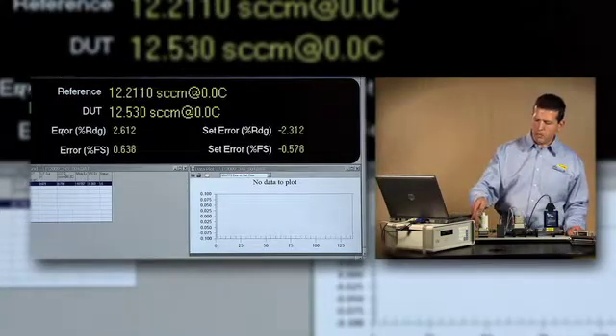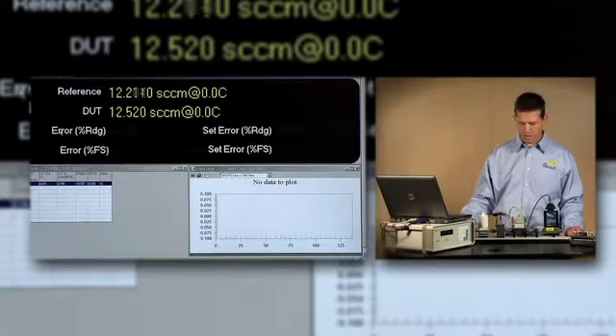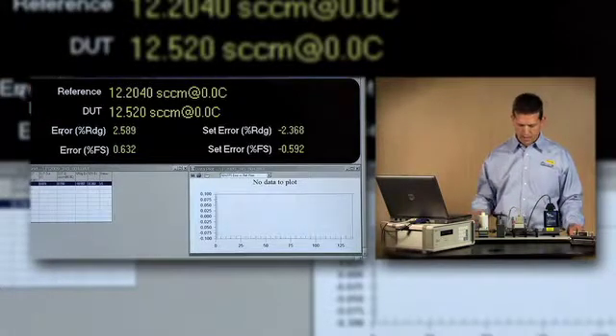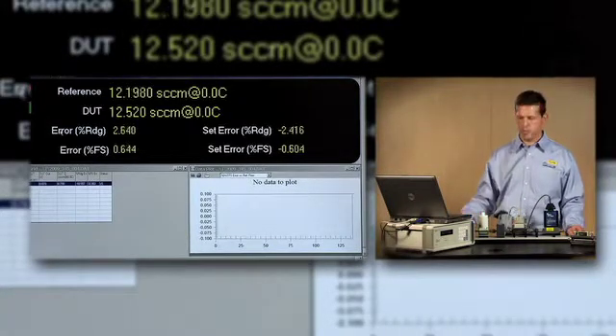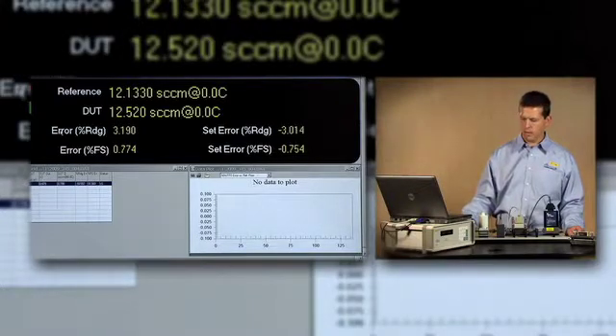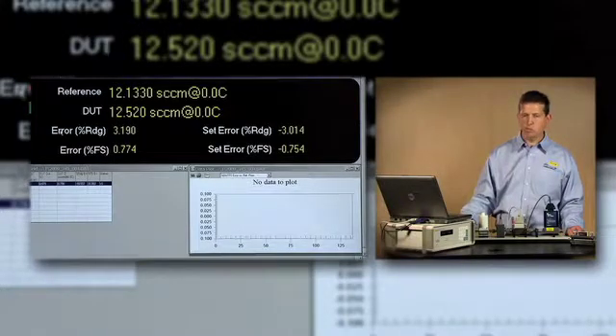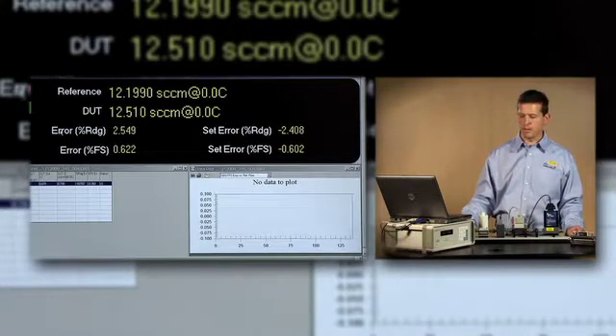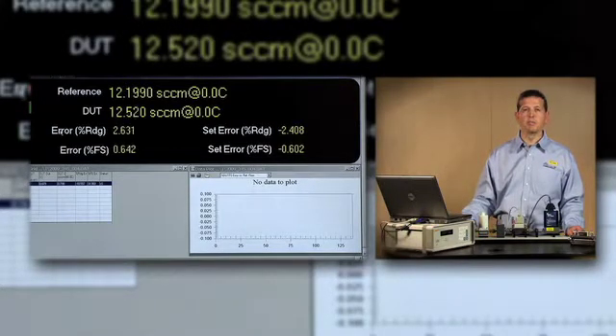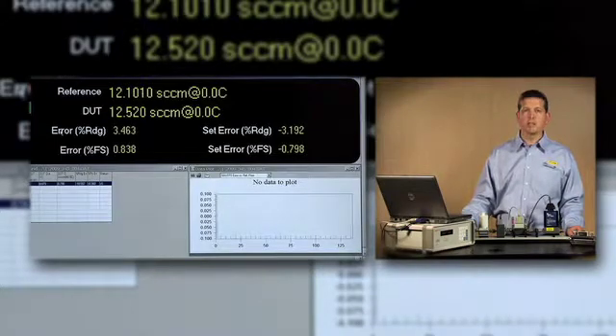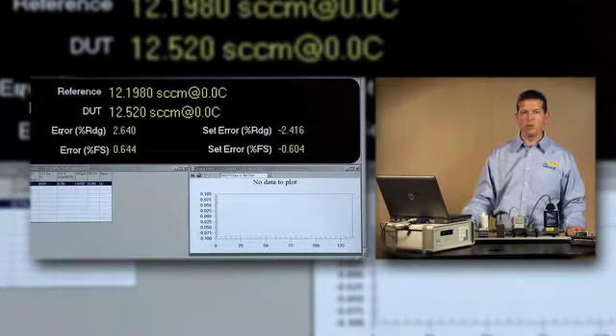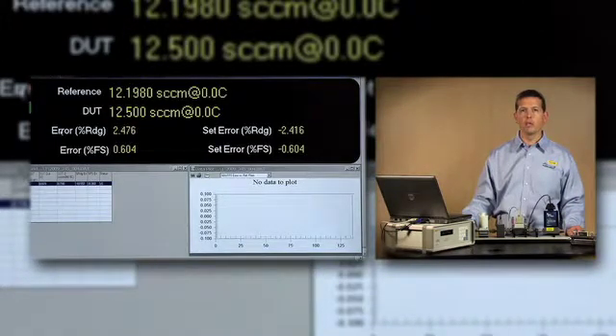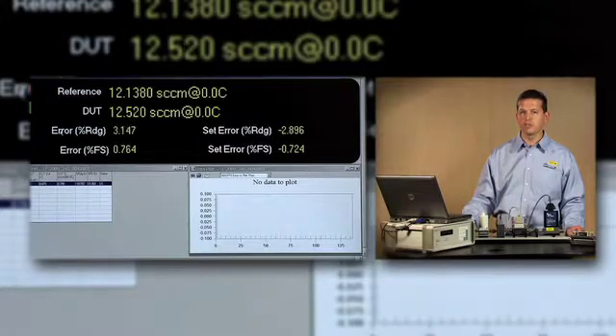The Molbox One Plus terminal is taking measurements from the molbloc, both pressure and temperature measurements, calculating flow. This is one of a couple of Molbox terminals offered by Fluke. We have the Molbox RFM, which is a smaller, portable, lower cost Molbox terminal.